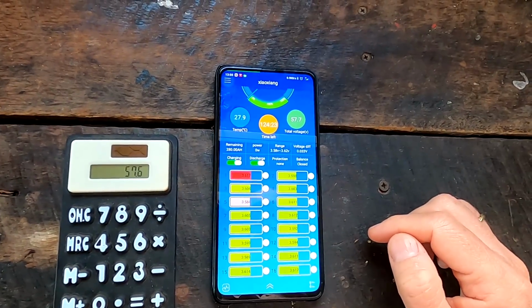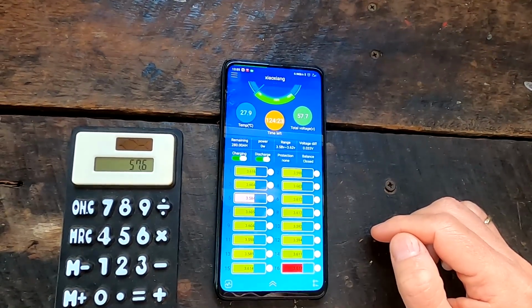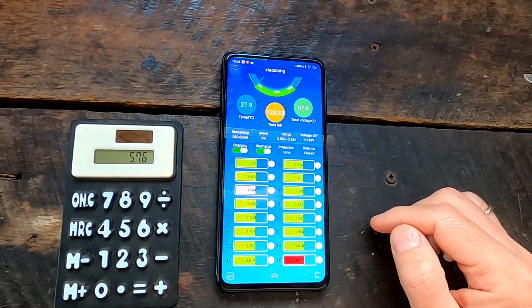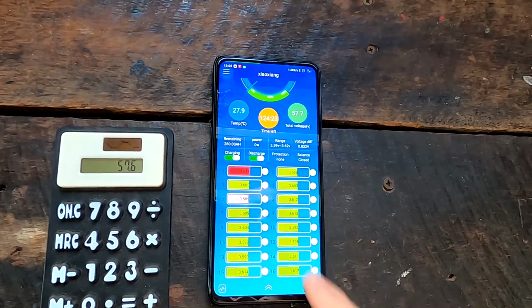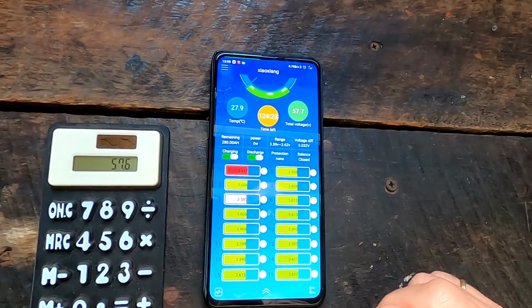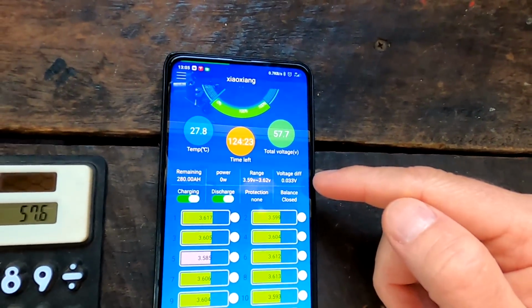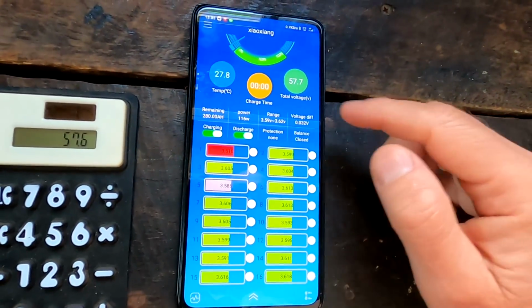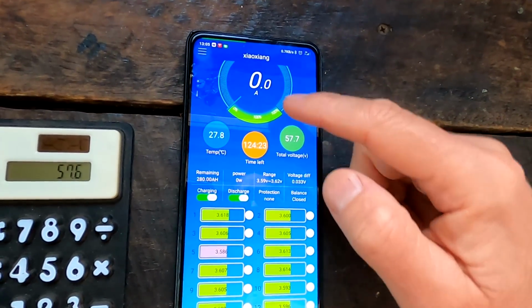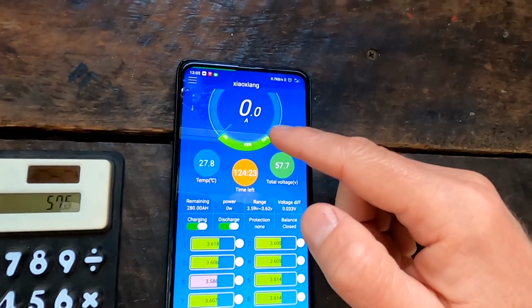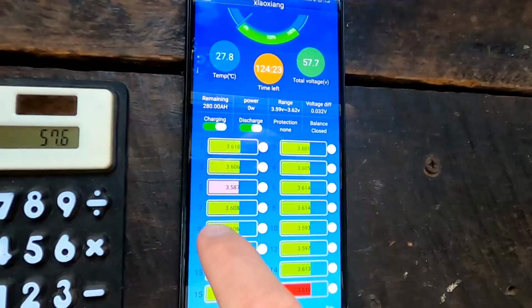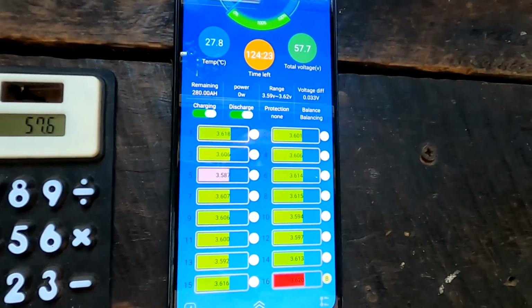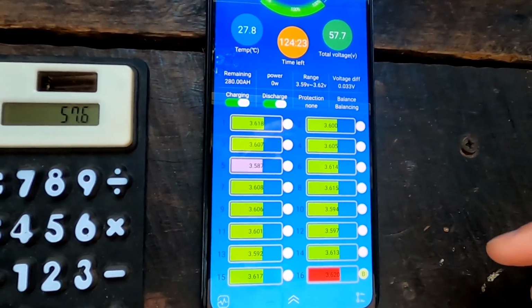Okay, we are still at 57.6 volts, which is 3.6 per cell. And we have now number 16 and number 1 on the same voltage, 33 millivolt deviation only, totally fine. It's only 2 amps, yeah, we can see here. Number 5 still needs to catch up a little bit, but voltage is increasing here, which is good.